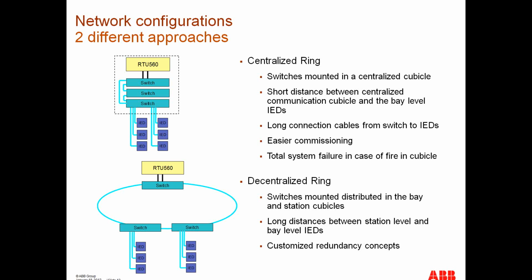You can see in the centralized ring that the switches are mounted together with the RTU in one cubicle, and this has the advantage that we have a short distance between the centralized communication cubicle with the RTU and the switches, but the cable lengths from the switches to the IEDs, which are in the bay level, are normally longer than in the decentralized ring, because in the decentralized ring you can put your switches where you want, which means nearer to the IEDs where you need them in the bay level at the end. So of course, if you have the RTU as well as the switches in one cubicle, it's easier to commission and to build the system up.